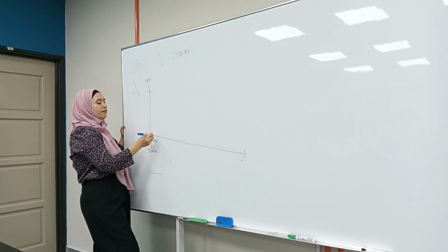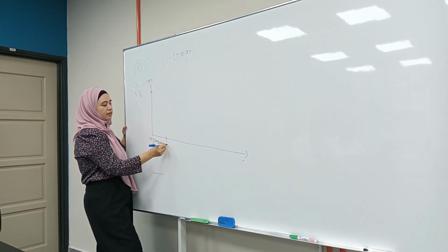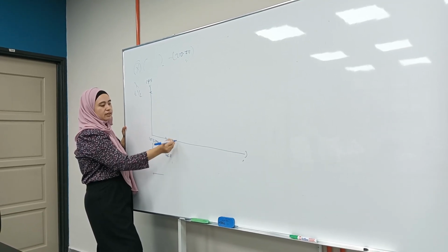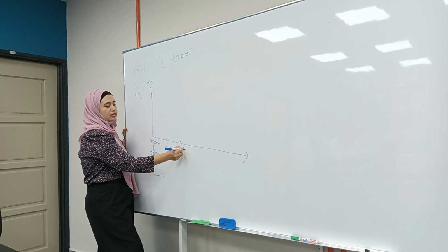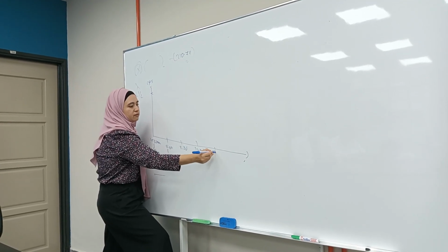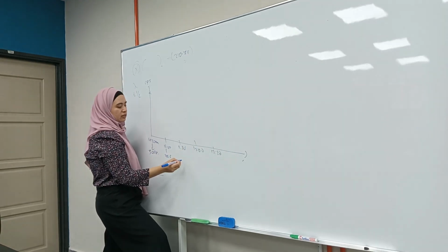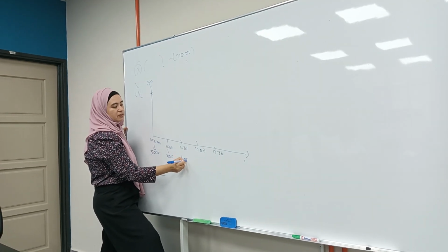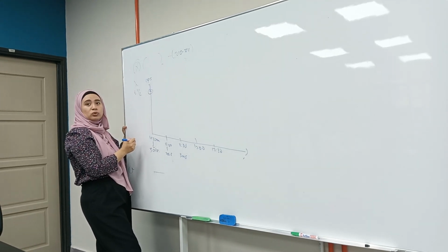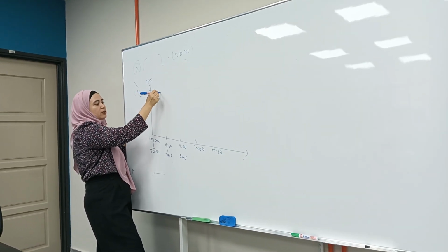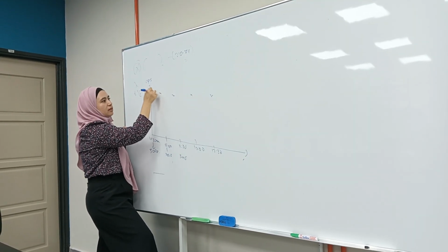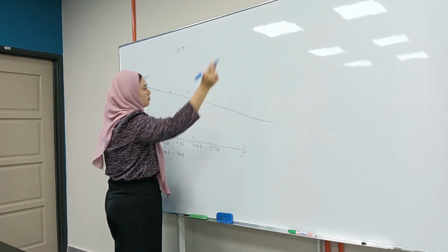Alright? And then at 11, you set the measurement again for 300 seconds. And then at 11:30, and then at 12, and then at 12:30. So you get all the measurements done at 300 seconds. But you have to record the total count. So it goes down a little bit, like that. And you can extrapolate that.